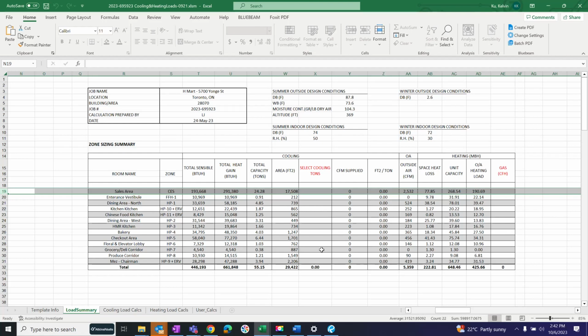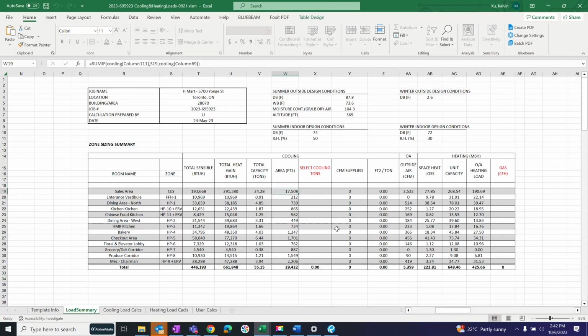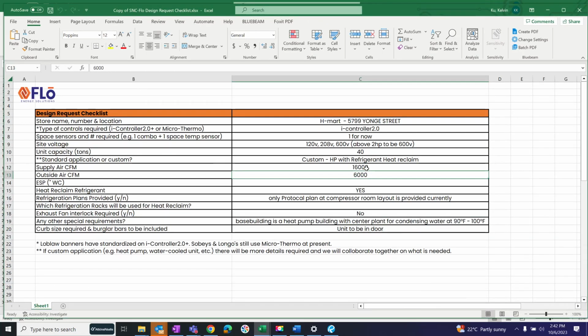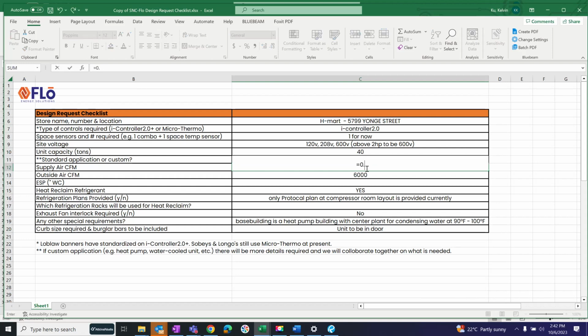I'm just trying to remember the grocery deli. No, that's still another heat pump too. I would imagine your selection tool guides you based on your loads, because that's really what it is. It's a relationship between the airflow needed and the load you're trying to accommodate. What we see in grocery, and I think Dave does this typically, is around 0.75 CFM per square foot, because grocery stores are typically always the same kind of loads. That ends up being a rule of thumb of where we land.